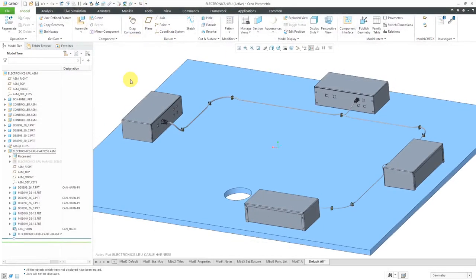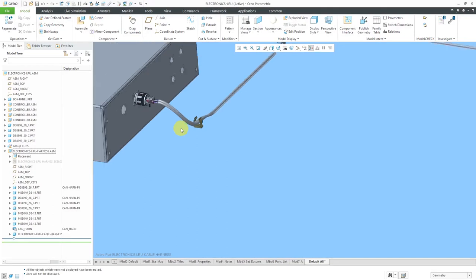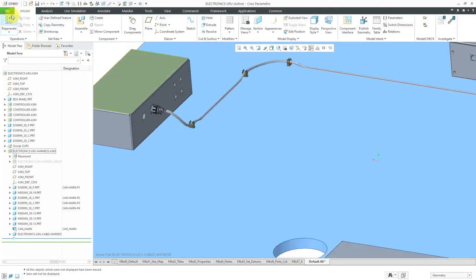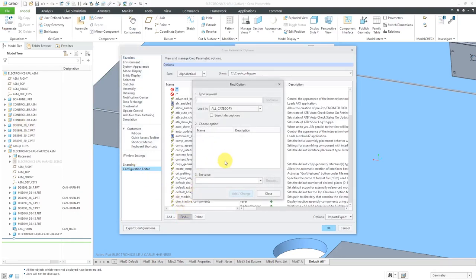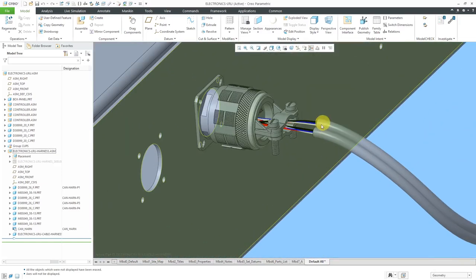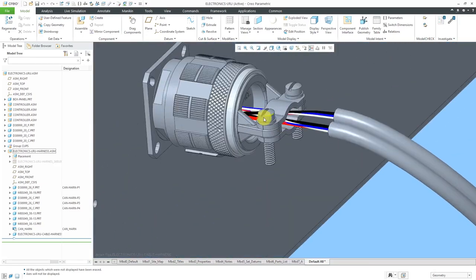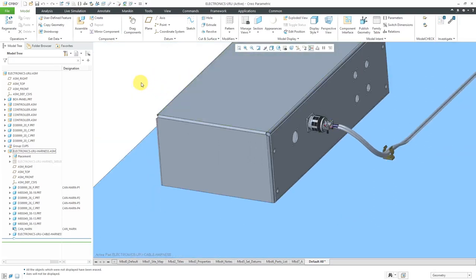Let's hit the close button and close out. Now we can see our cables routed through at the top level of the assembly. One last thing to mention: a config.pro option related to jackets. Go to File, Options, Configuration Editor, hit Find, and search on the keyword 'jacket'. There is a config.pro option called cable_jacket_termination — the default value is network ends. The other option is ports. If you change it from network ends to ports, then when you route using the network, instead of the jacket stopping at the last network point, it'll go all the way into the entry port. You can also adjust those network location points if you want the jacket going closer to the entry ports.